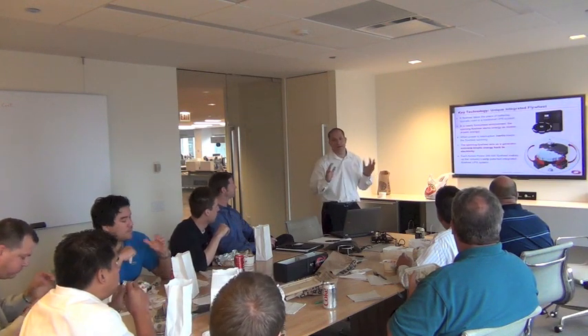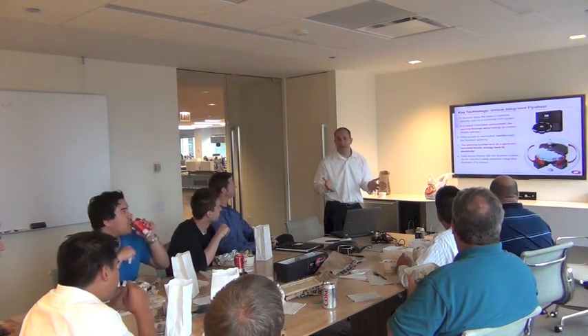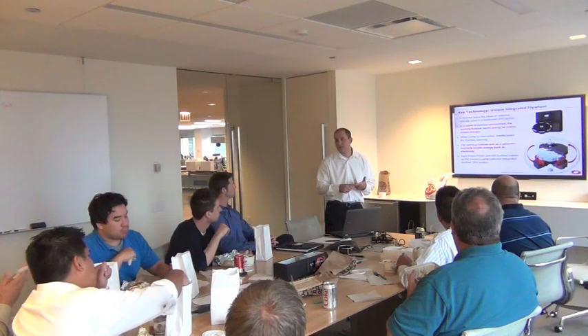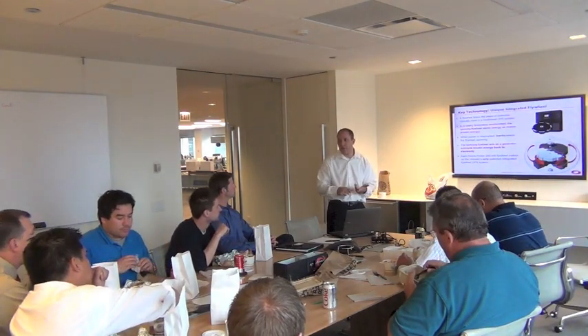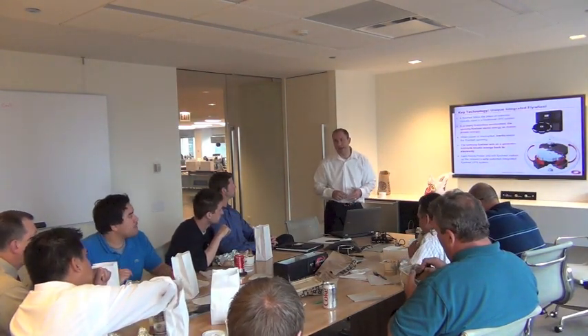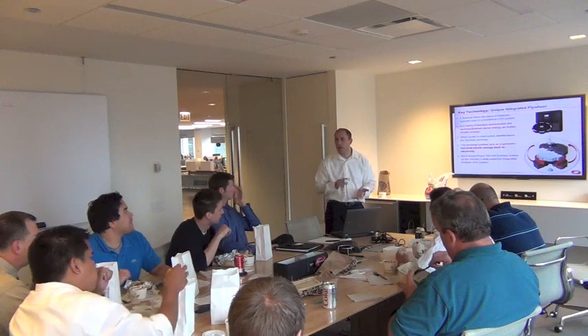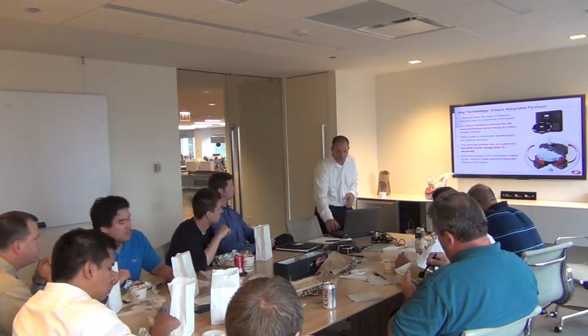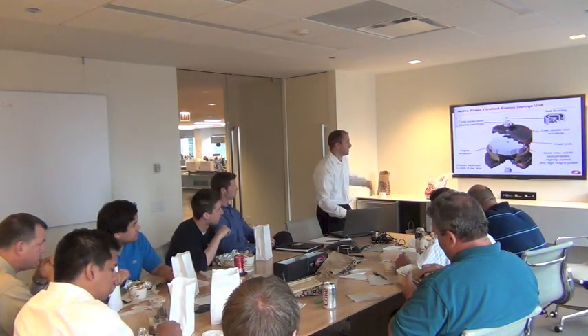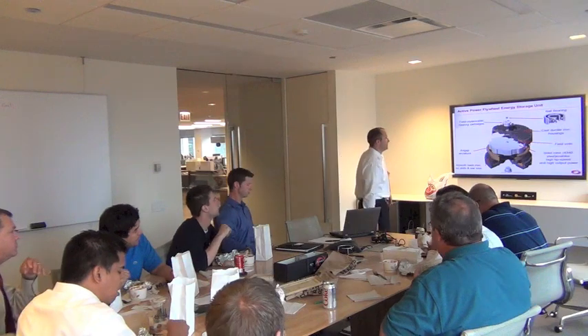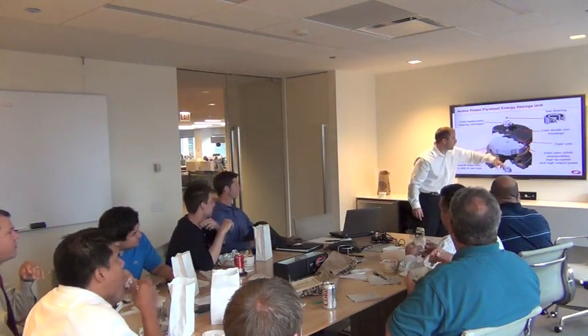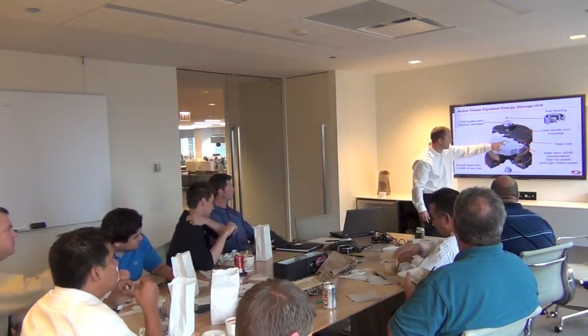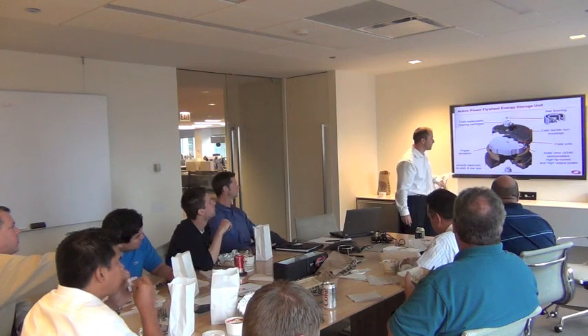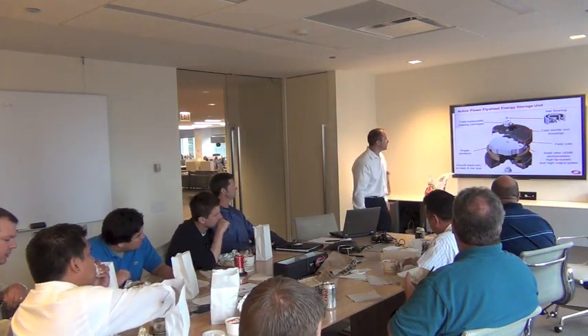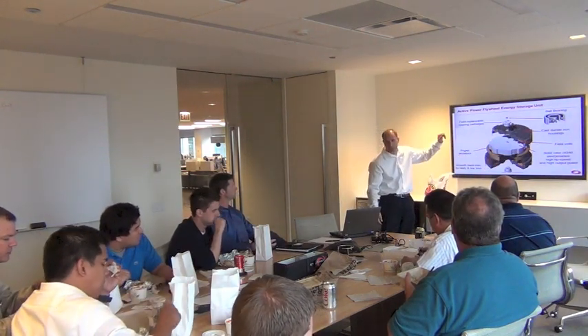The UPS, as an integrated package, is about 97.6% efficiency. So there are some additional losses in the UPS, obviously from inverters, rectifiers. There are some fans. There's a very large choke in each flywheel cabinet as well. We'll kind of get into the topology. This is actually a better picture of the buck. So you can see the upper and lower field coils, the casting, the 4340 rotor, the 3-phase armature. It's actually a little bit better picture. And again, once every 4 years, you're going to change the bearings.